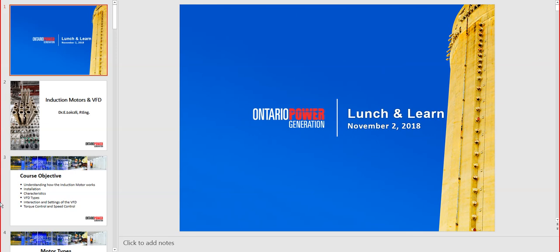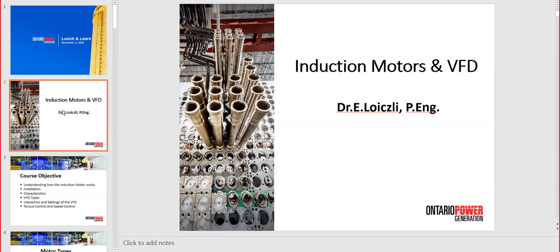I will go over the slides, but really I also have a manual that is like 100 pages and has all the information you need to know about VFDs. So variable frequency drives are used for speed change of the motor, induction motor typically. So what we're talking about here is induction motor speed change. Very well can be used for other types of motors. We have drives for DC motors, we have drives for synchronous motors, but most of the time when we talk about VFDs, those are variable frequency drives, and they are for induction motors mostly. In the plant we have applications for different fans and other things that need to have variable speed, also variable torque.